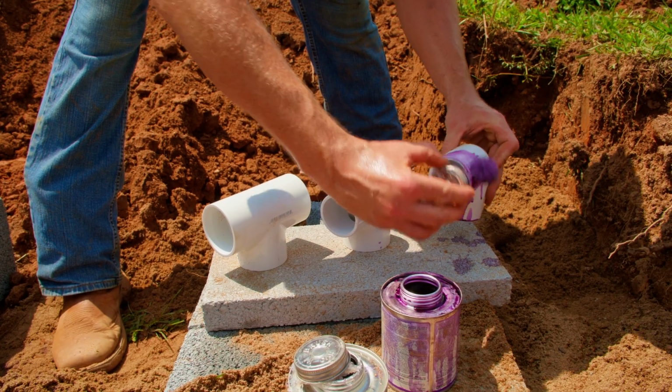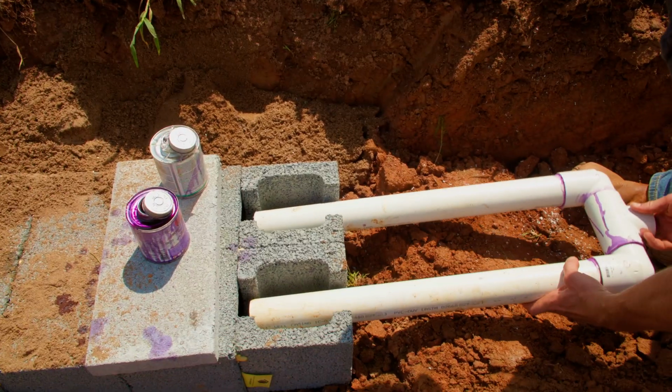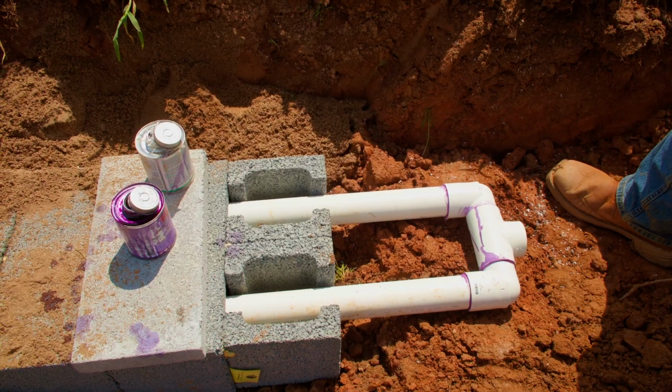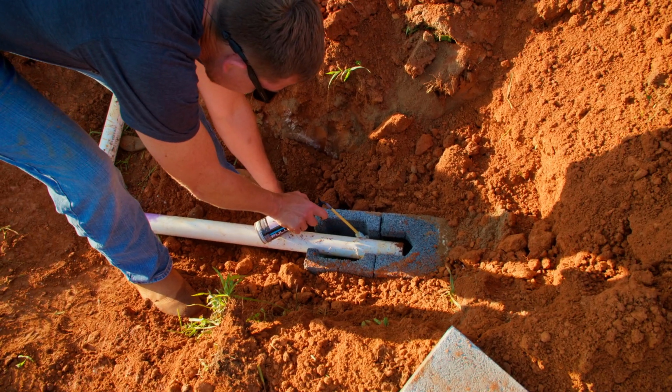Then, for horizontal panels, you might be using an entry tee to split that 2-inch supply line into two pieces and shotgun feeding that first horizontal panel in each line. With vertical systems, you will simply take this 2-inch supply line all the way to the first panel block and plumb it into the first panel.